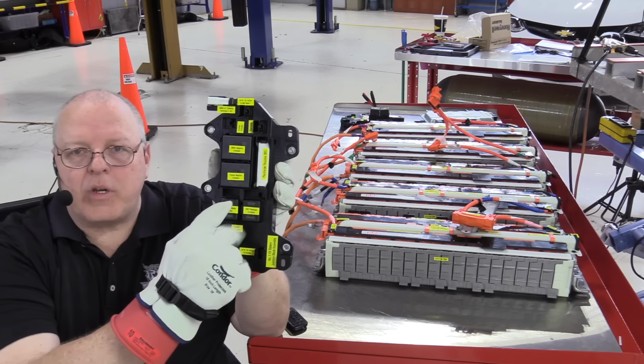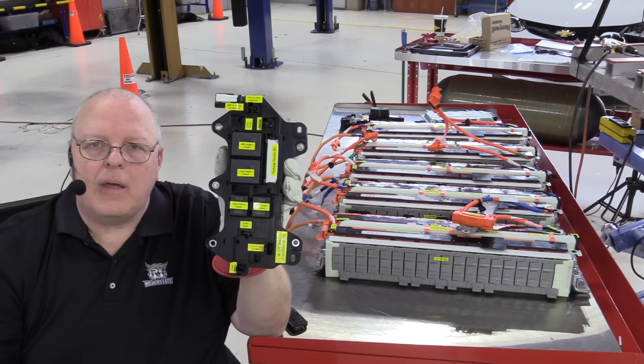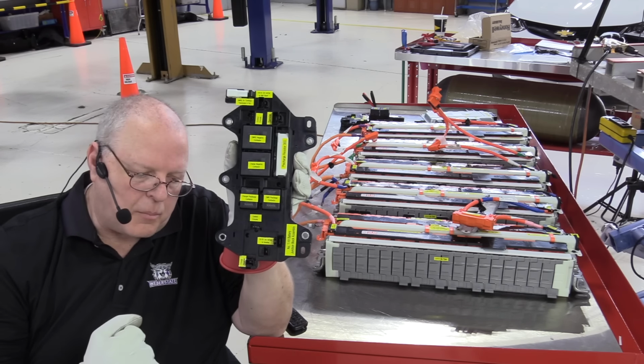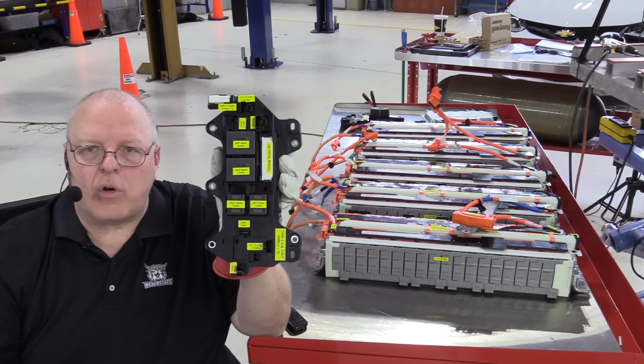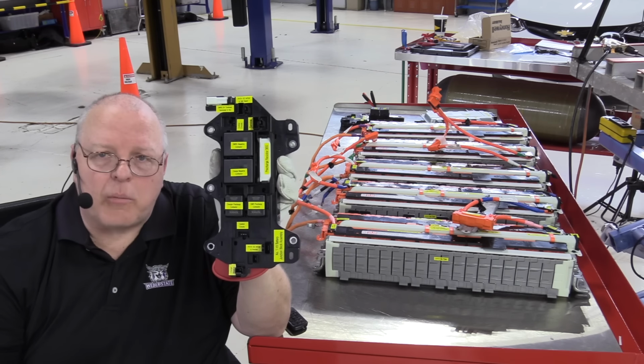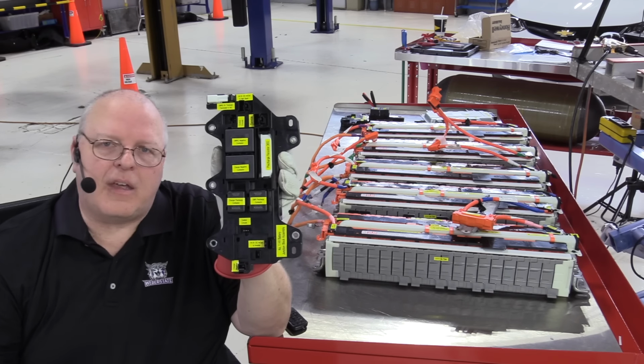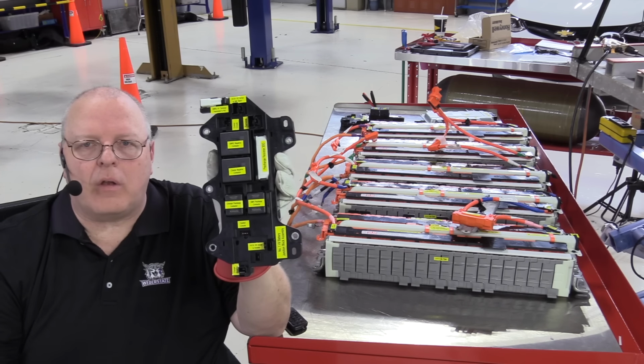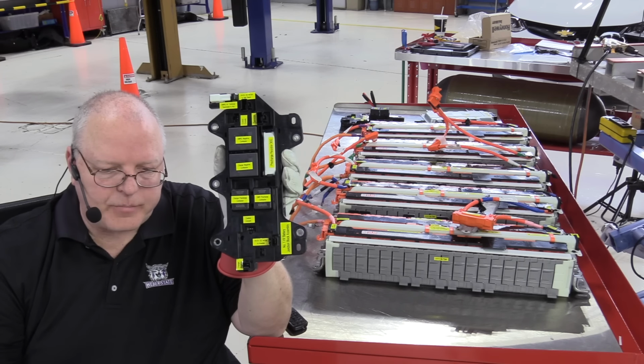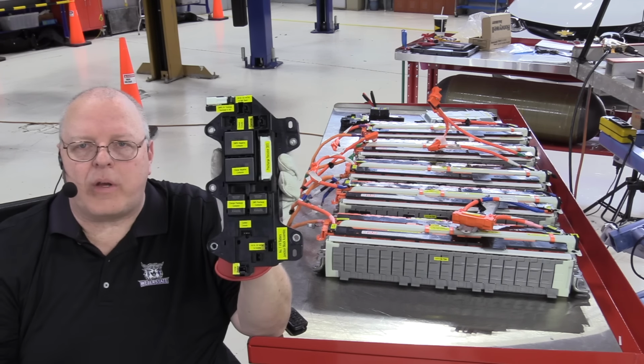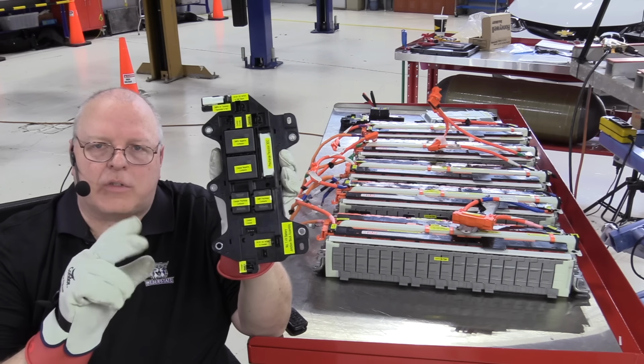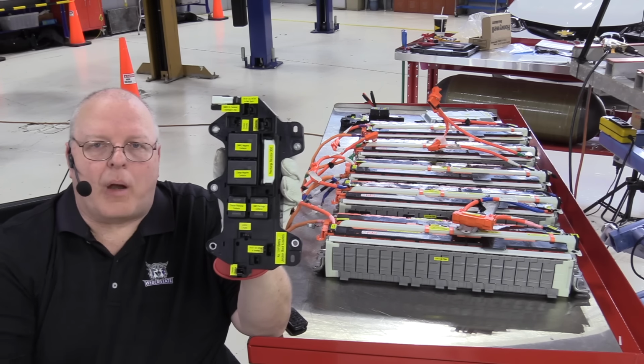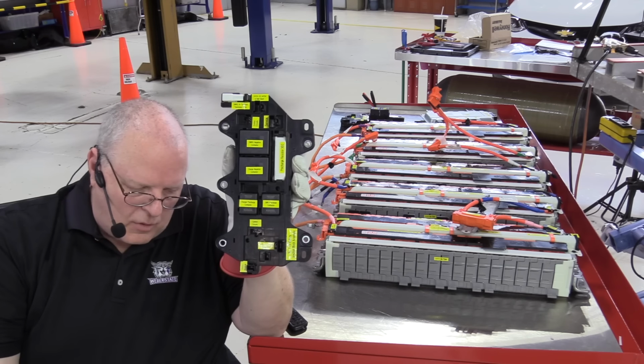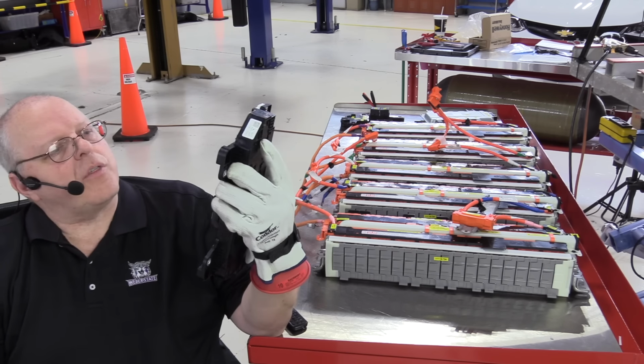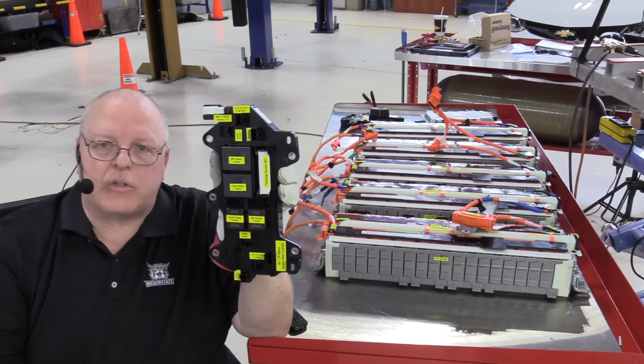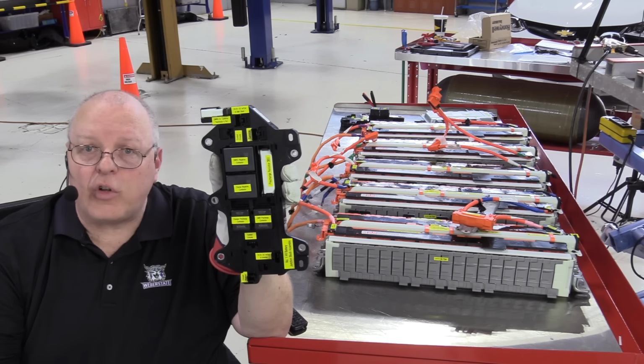And the job of the pre-charge contactors and resistor is to prevent the capacitor in the inverter assembly, the smoothing capacitor, from charging too quickly, giving a surge or a rush of current that could actually damage the contactor points as they are closing. They can actually arc. And so by running it through a resistor here, and this is a 30 ohm resistor, it slows that down, allows the capacitor to fully charge.